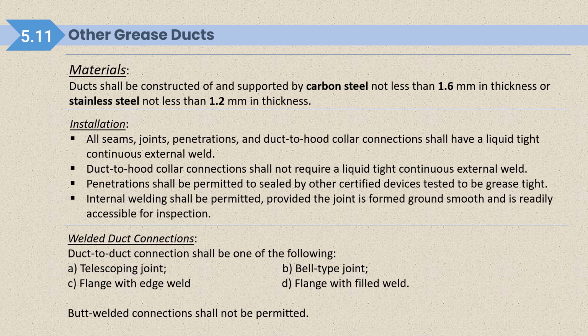Welded duct to duct connections shall be one of the following: telescopic joint, bell type joint, flange with edge weld, or flange with field weld. But butt welded connections shall not be permitted while connecting the duct.